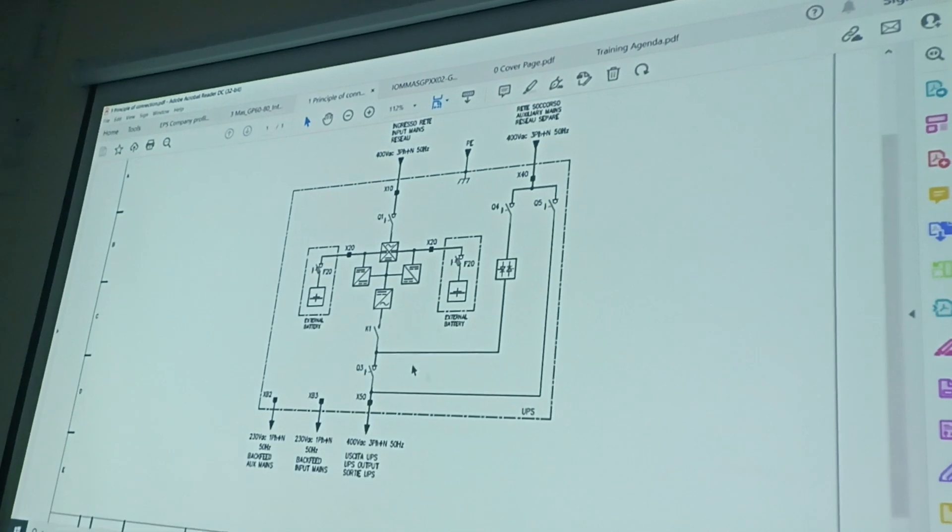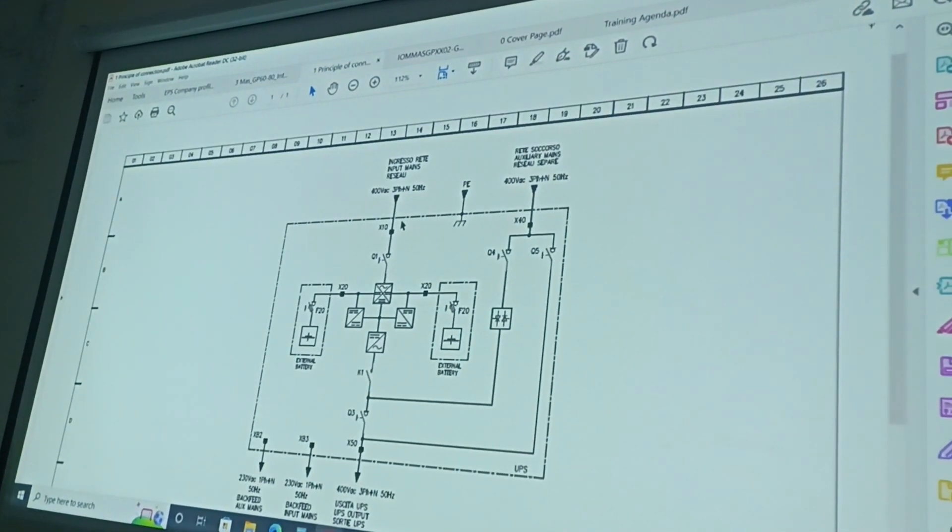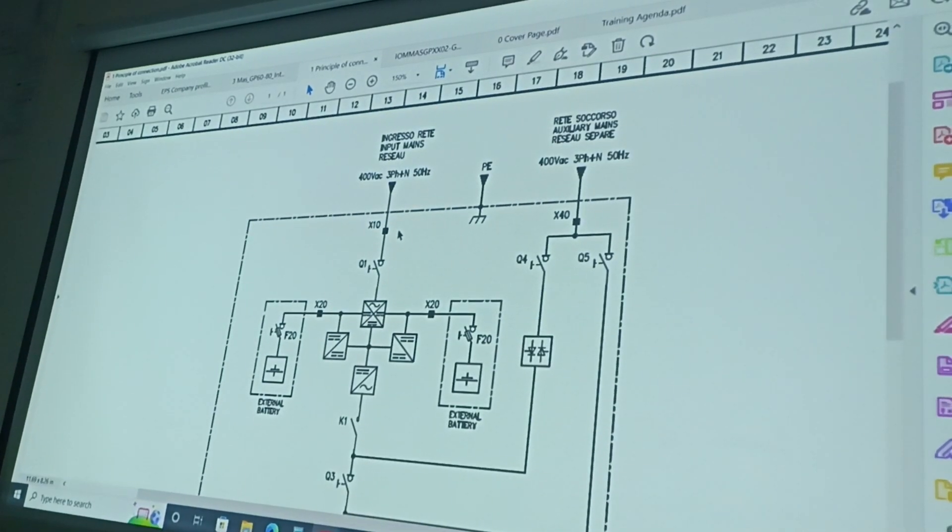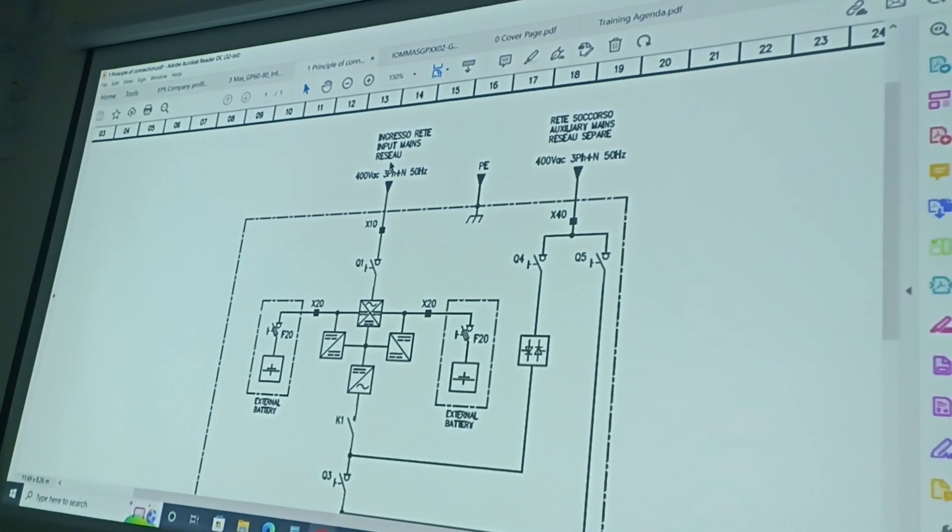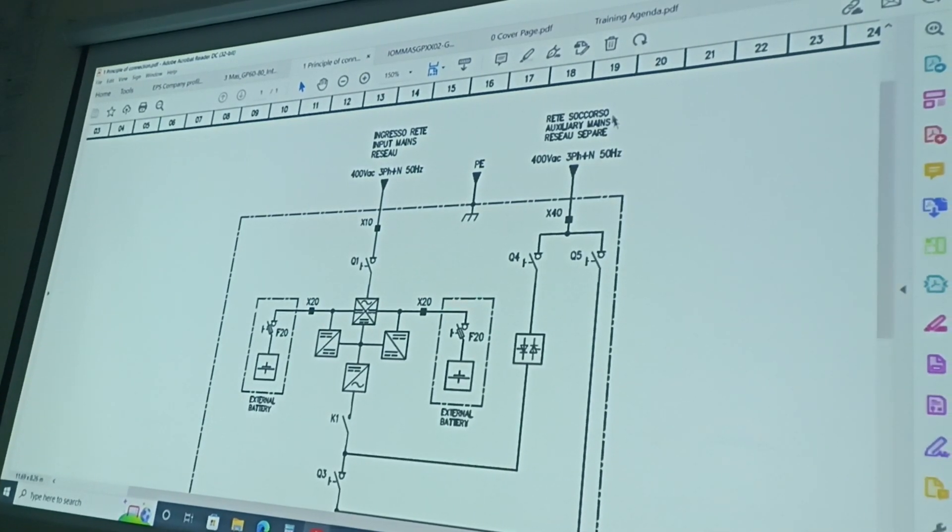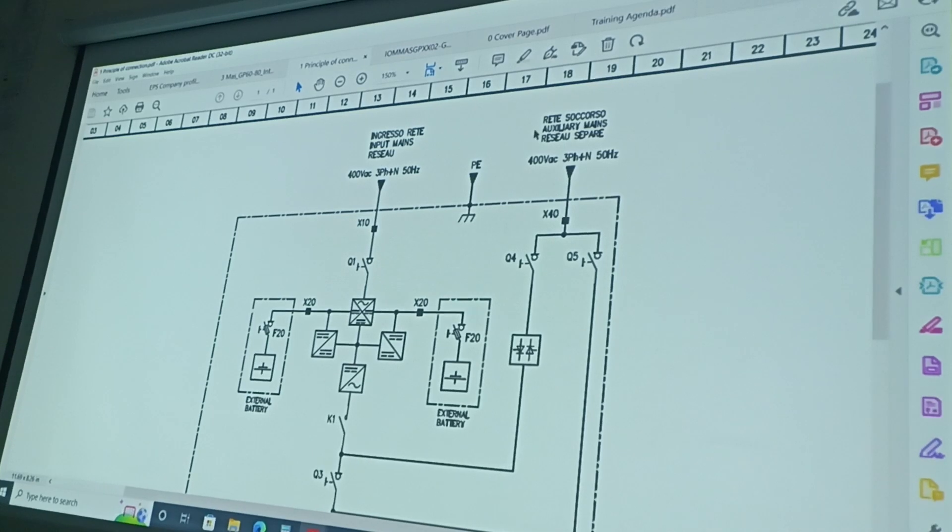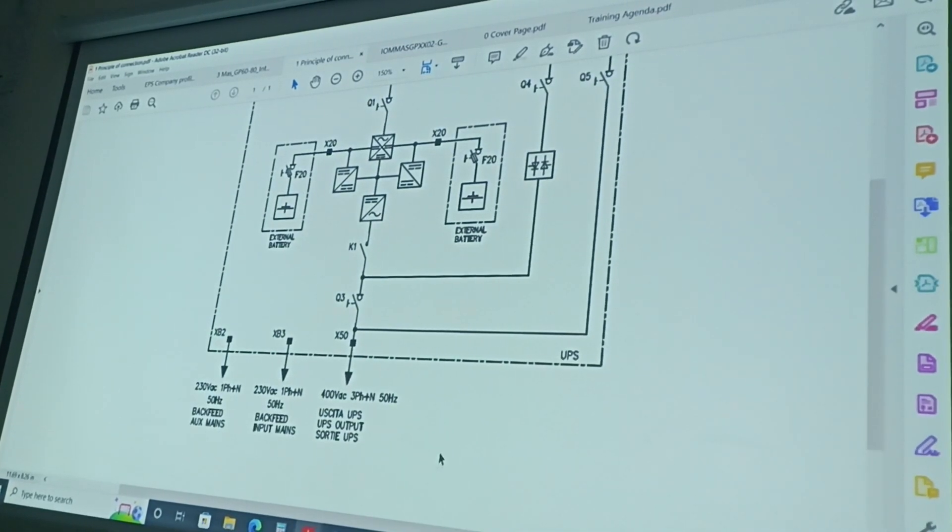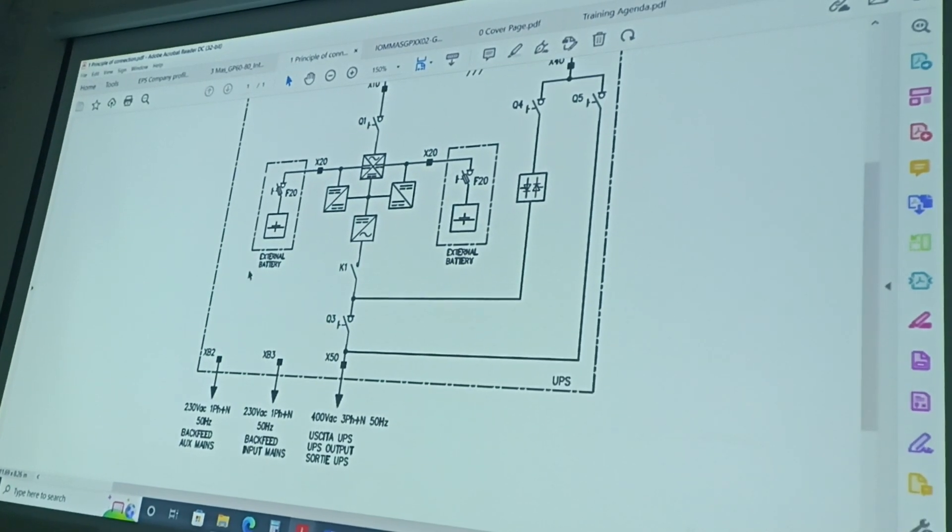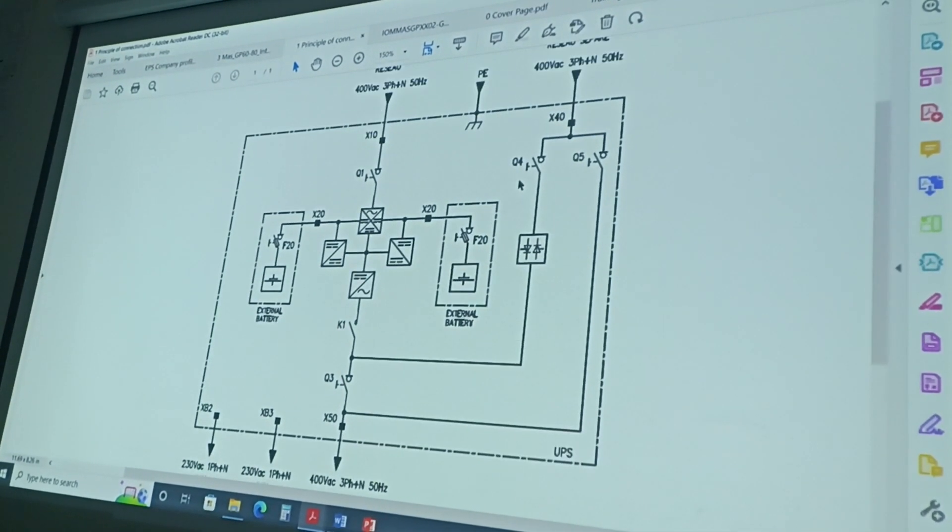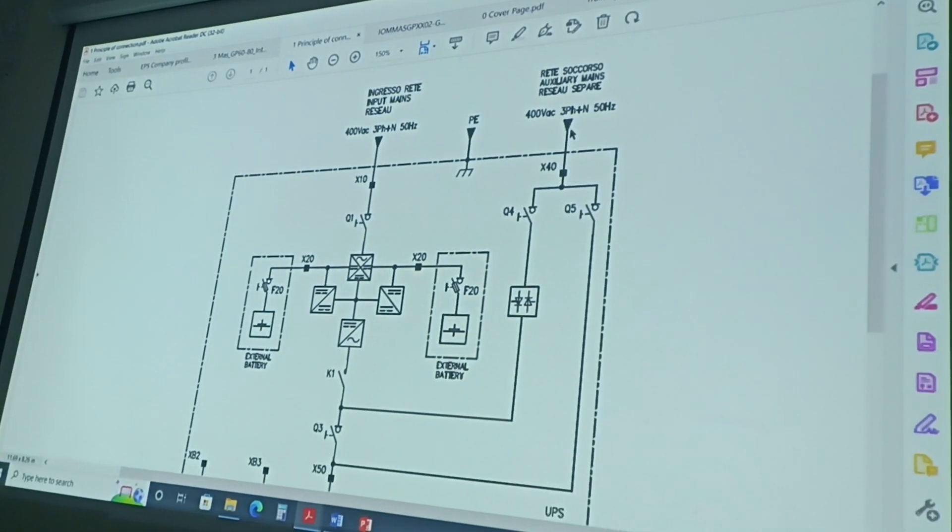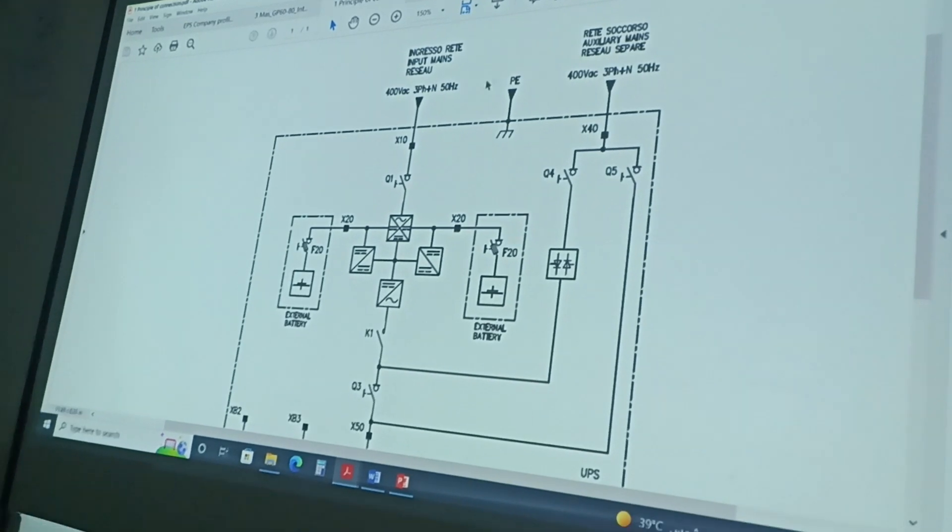So in this unit, as we said, we have from the input side two connections. Exactly. For the input, and for the auxiliary part, or the bypass. And here, the internal bypass, is it connected to the same source, or a separate source? Here, it's connected to the same source. So there's a jumper between them? Exactly. There's already a jumper made on the outside.